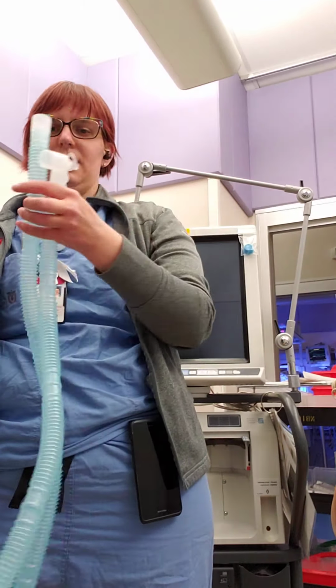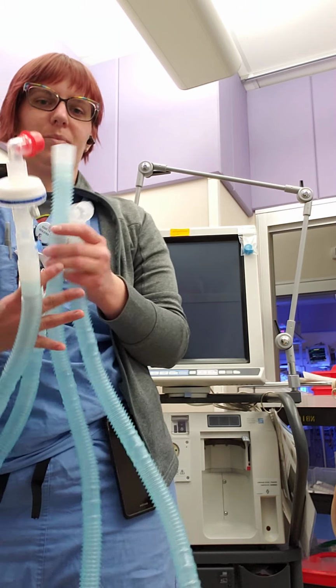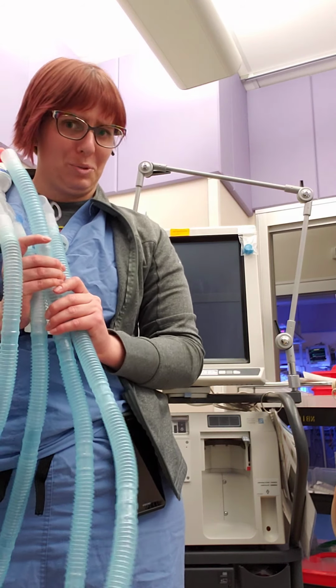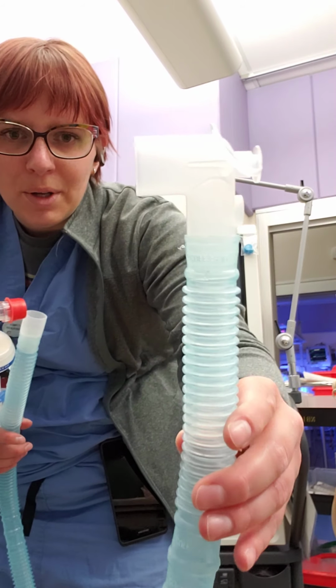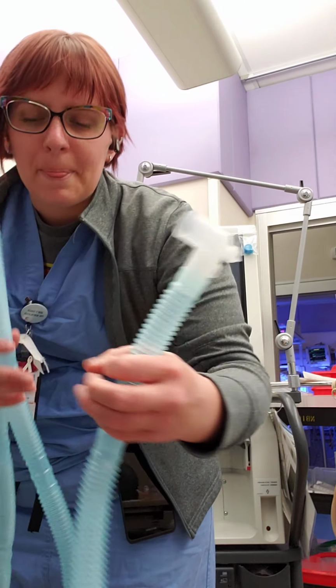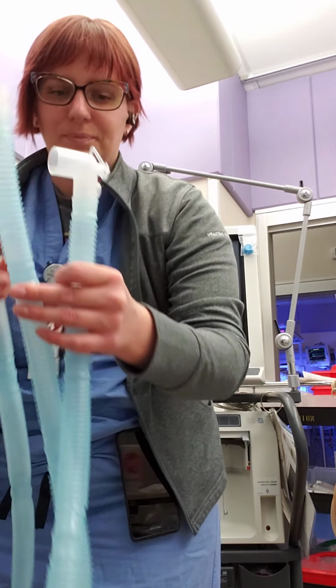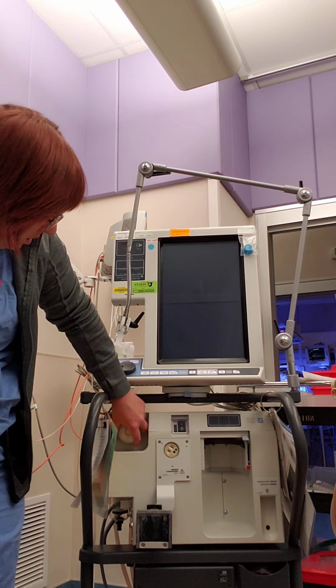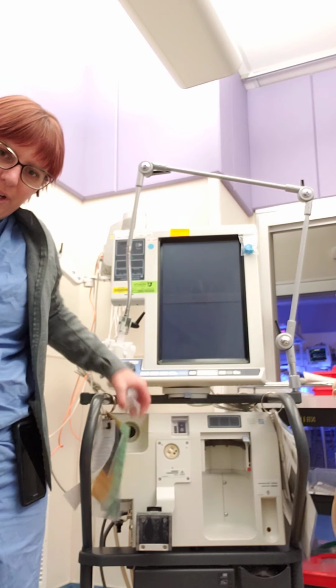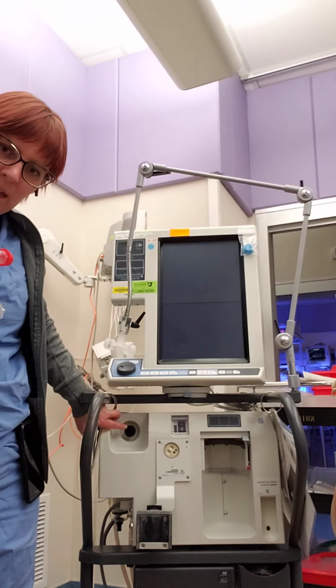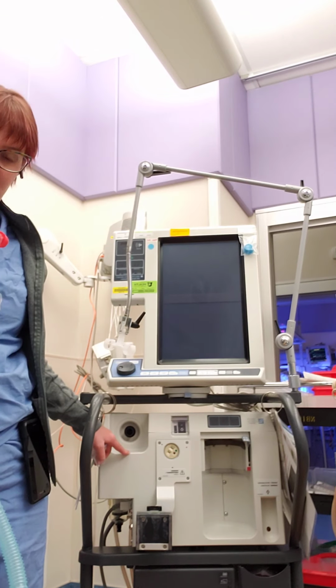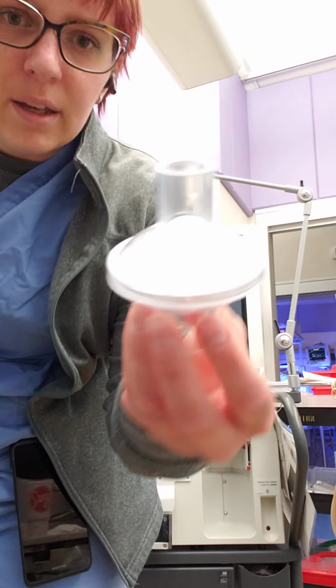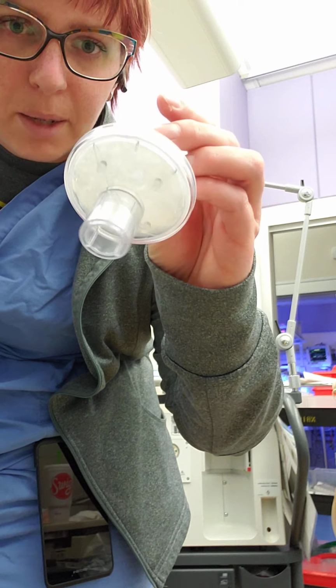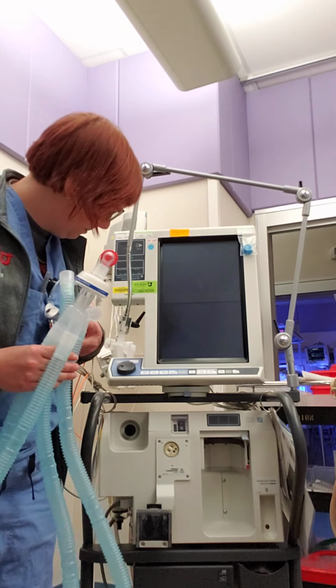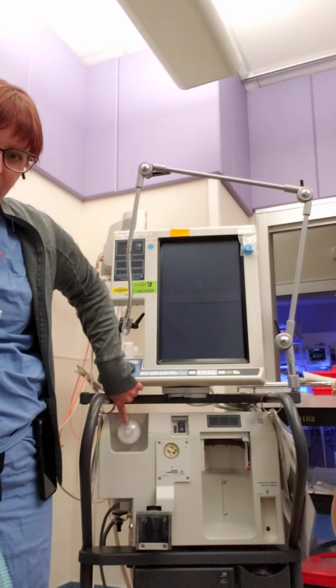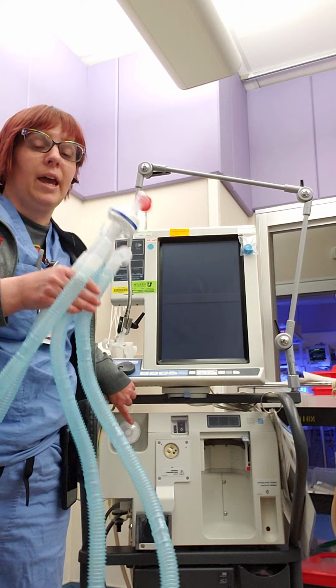So we start at one end and move to the next. Say you pull it out and you think, I'm not really sure which one goes where. The one with the 90-degree elbow is your inspiratory limb. The straight is your expiratory limb. Over here is your inspiratory flow valve. And it will say to patient, and there's an arrow showing right here. Next we take a filter. This is also a viral filter that's also 99.9% effective to block against bacteria and viruses. You first place the bacterial filter right here so that we can both protect the patient and the equipment for future use.